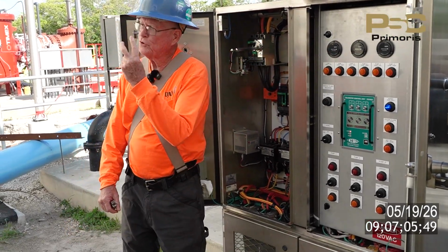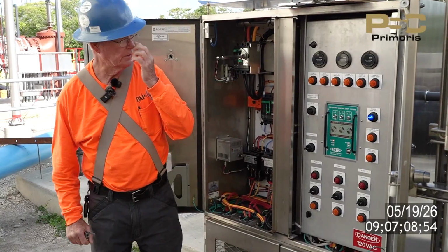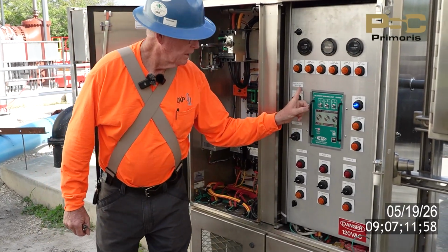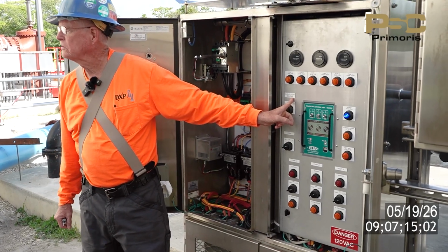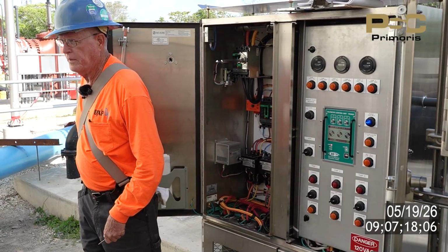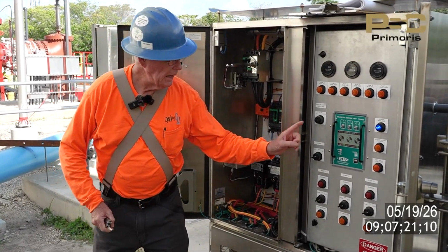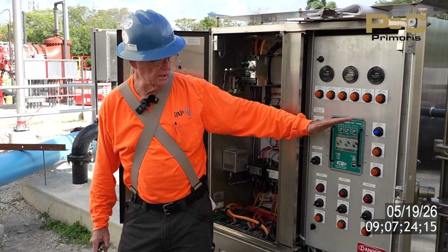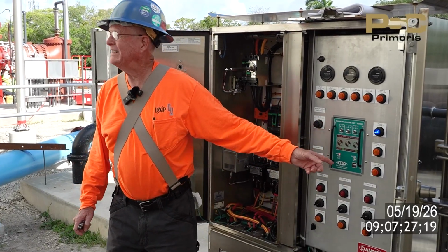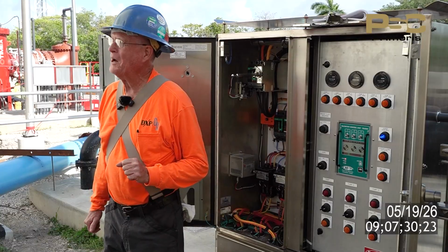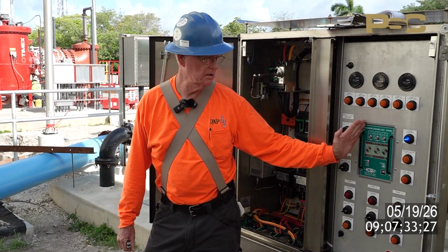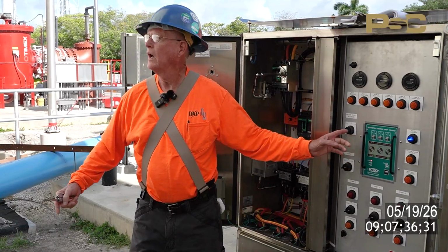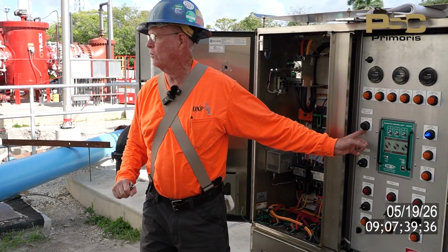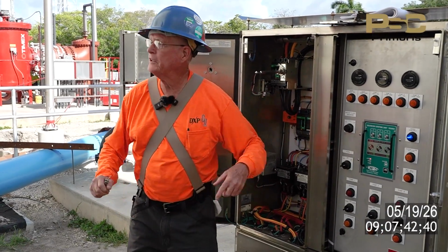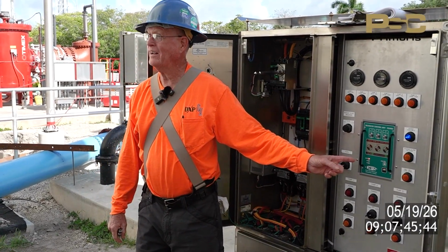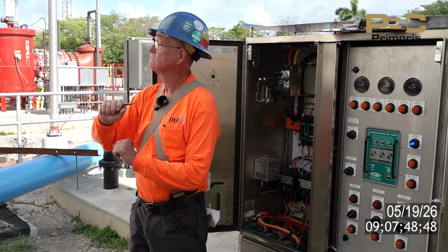Then you've got two sections for control. Number 1 is the backup float sequence—you have float balls in the wet well, so if I lose my telemetry unit and it dies, it'll work off the floats. The telemetry control unit is primary control, the floats are secondary control. So if you turn the three switches off, that becomes dumb, and I'm just looking at my floats to come on and off.